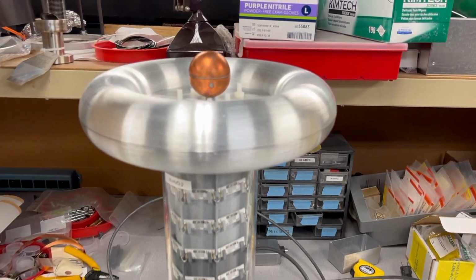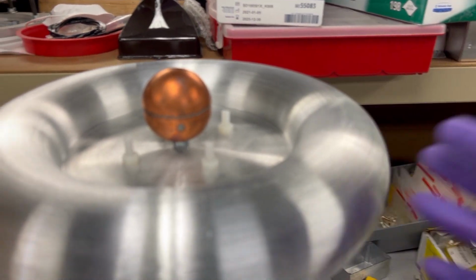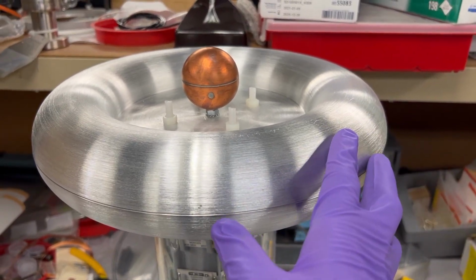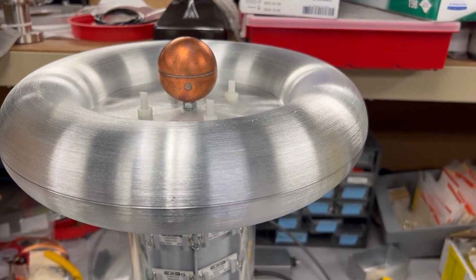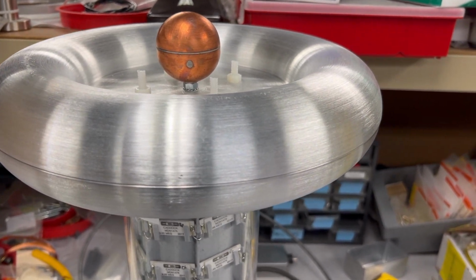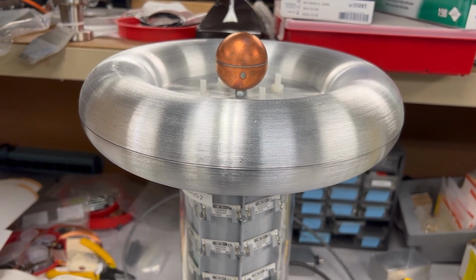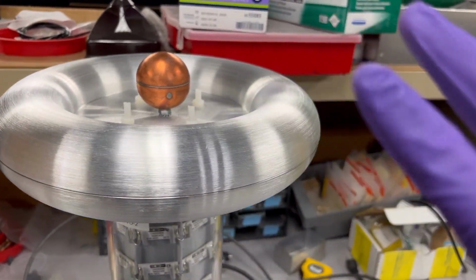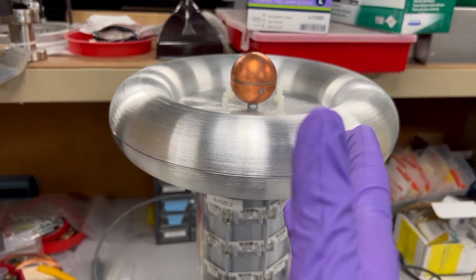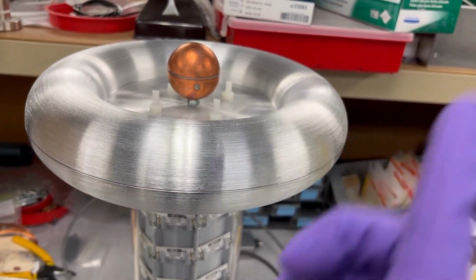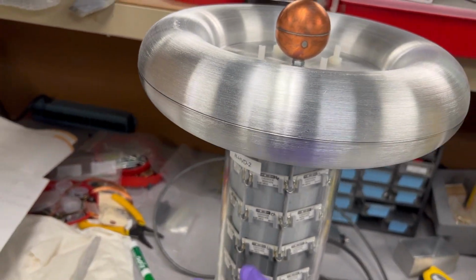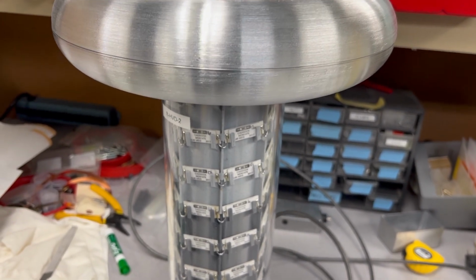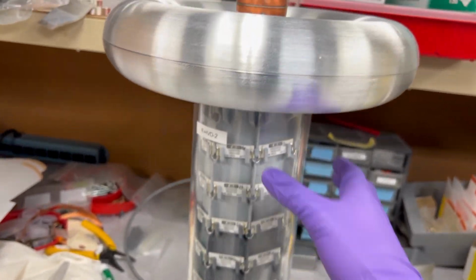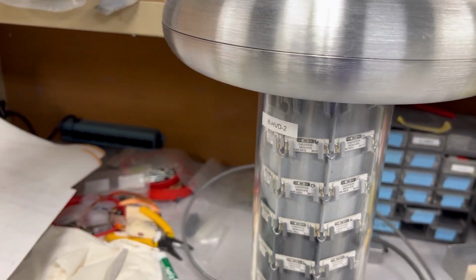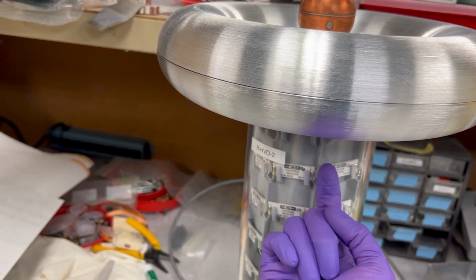Starting at the top, we have this copper ball and aluminum toroid-shaped top load, and this is to ensure an even distribution of the electric field because we're applying such a high voltage across the divider. If there were any pointed edges or sharp corners, that would have a high potential which could cause arcing and potentially damage electrical components.